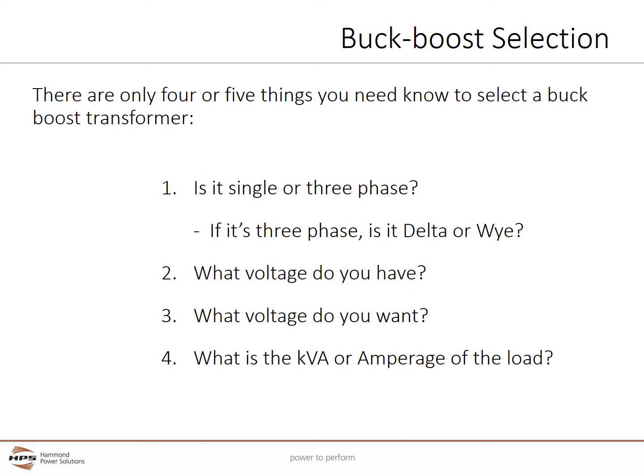There are only four or five things you need to know to select a buck boost transformer. First, is it single or three-phase? If it's three-phase, you need to know if the circuit is delta or Y. Second, what voltage do you have? Third, what voltage do you want? Fourth, what is the kVA or amperage of the load? Using the buck boost selector, you don't even need to remember this — just fill in the blanks.